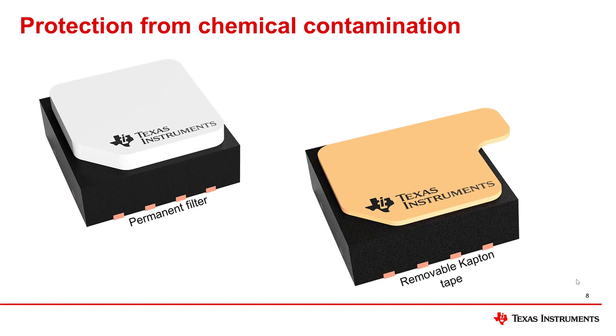Typical ambient conditions do not present a significant risk for chemical exposure, but manufacturing and storage environments are a known source of volatile contamination. During assembly, a piece of Kapton tape can be placed over the sensor opening to ensure that the device is not exposed to harmful chemicals. A permanent hydrophobic filter is a good option if the sensor will be exposed to dust, debris, or condensation during application.